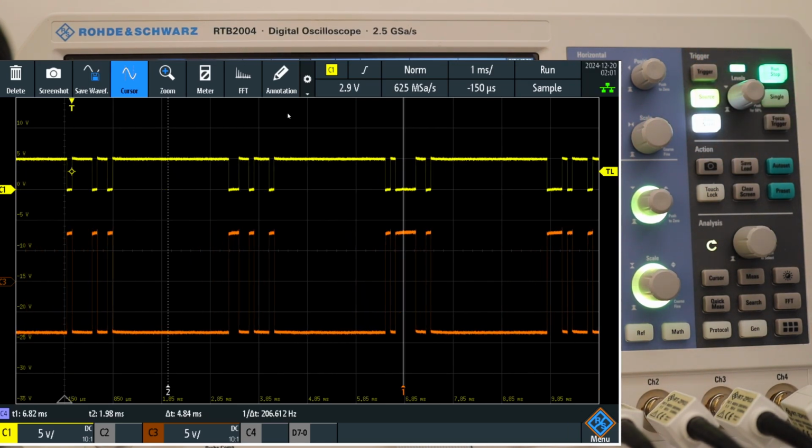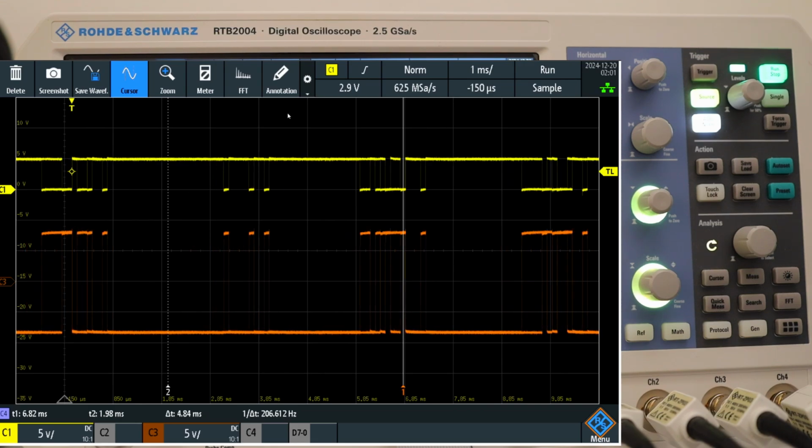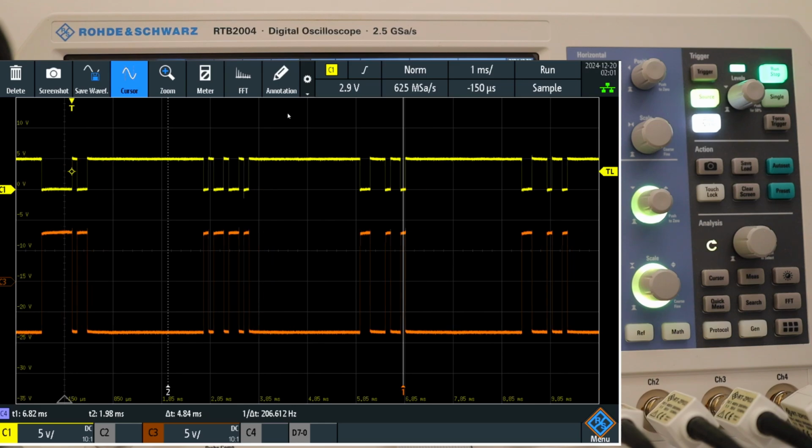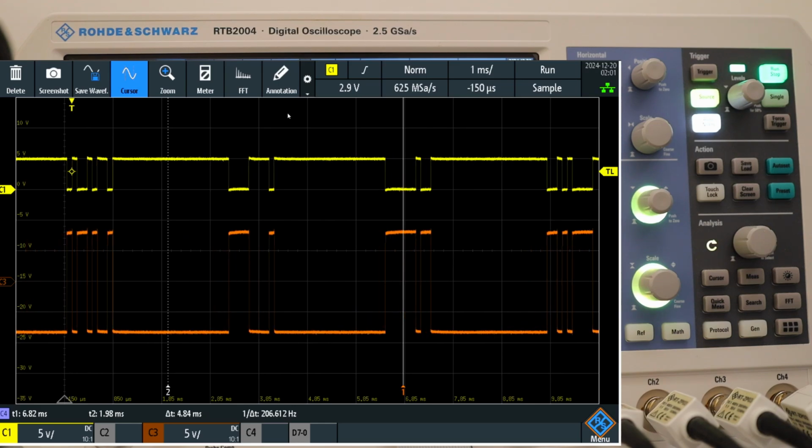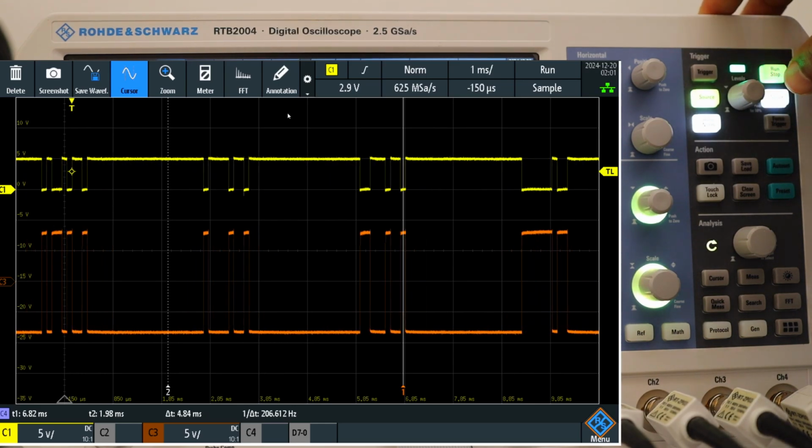This kind of trigger that is jumping around is not acceptable. You cannot deal with this kind of signal, and one basic method to deal with digital signals is setting up a pulse trigger. So let's set up a pulse trigger. Let's do a single capture first.